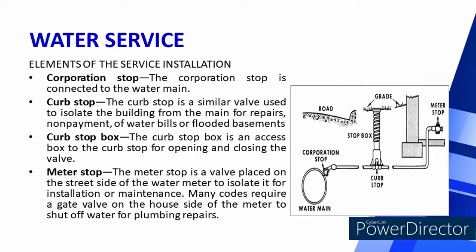Elements of Service Installation: First is the corporation stop, which is connected to the water main. Second is the curb stop, a valve used to isolate the building from the main for repairs, non-payment of water bills, or flooded basement. Third is the curb stop box, an access box to the curb stop for opening and closing the valve. Last is the meter stop, a valve placed on the street side of the water meter to isolate it for installation or maintenance. Many codes require a gate valve on the house side of the meter to shut off water for plumbing repairs.